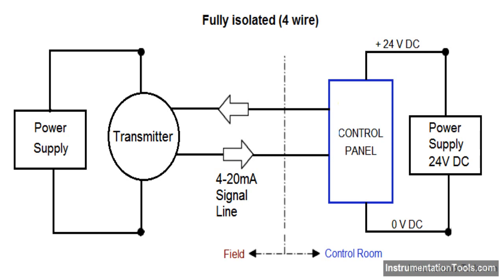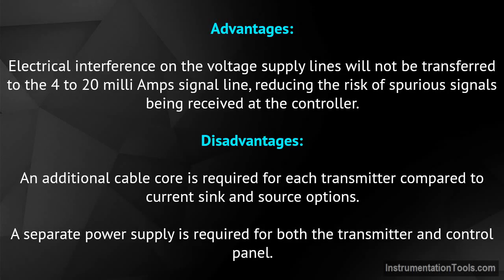Four-wire fully isolated transmitter. The transmitter and control panel use separate power supplies. The 4 to 20 milliamp signal flows through two separate cable cores between the transmitter and control panel. Advantages: electrical interference on the voltage supply lines will not be transferred to the 4 to 20 milliamp signal line, reducing the risk of spurious signals being received at the controller.